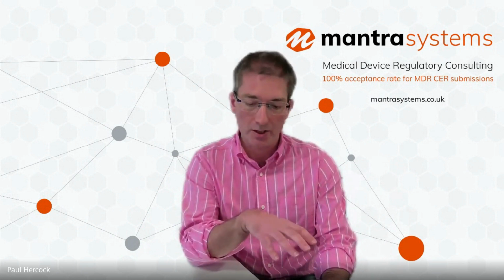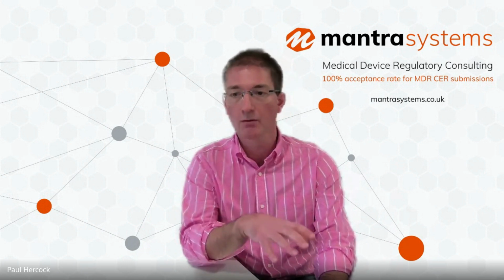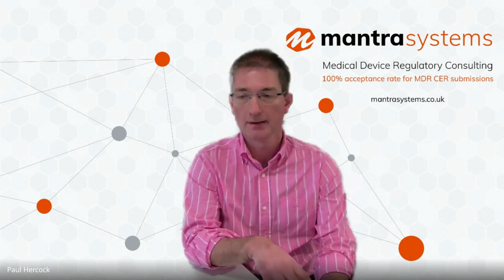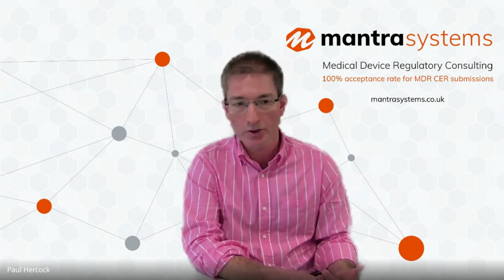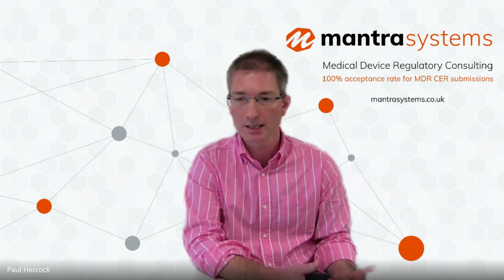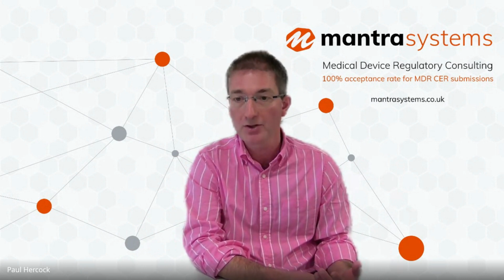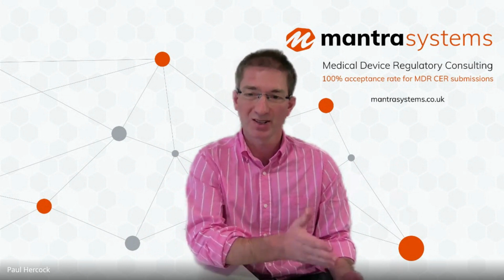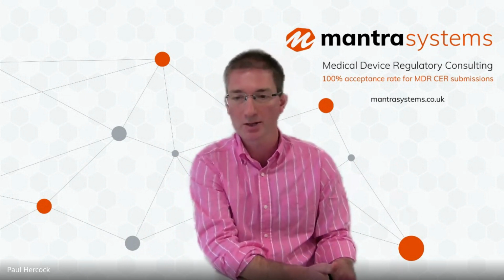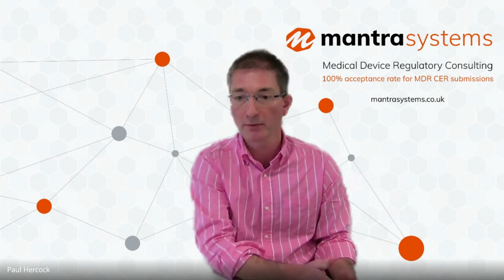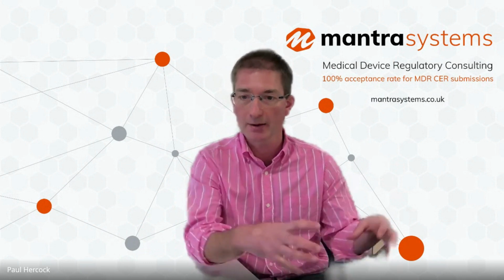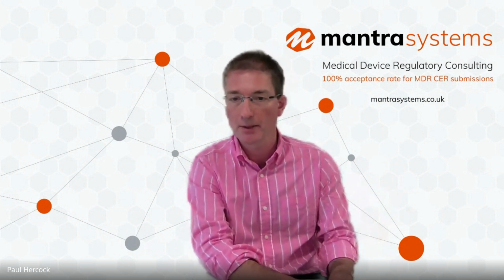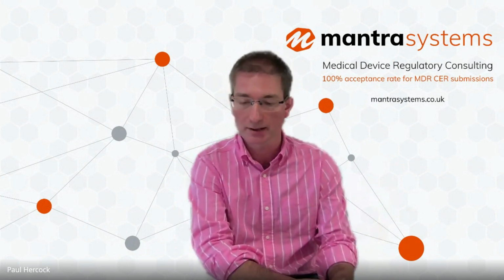The next section, it's a good idea to list any relevant harmonized standards. And then the way we structure it is that section 6 is a detailed exploration of the evidence related to state of the art. This is a really critical section because this is where you get your safety and performance objectives, ideally down to single numbers for each parameter based on a weighted analysis.